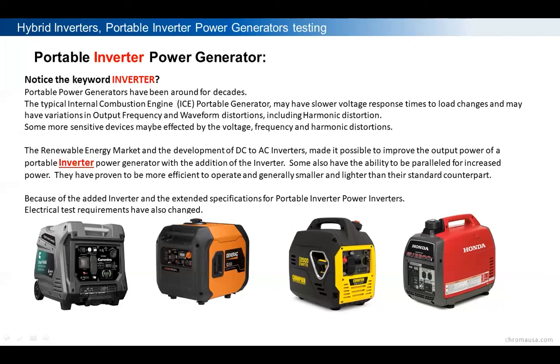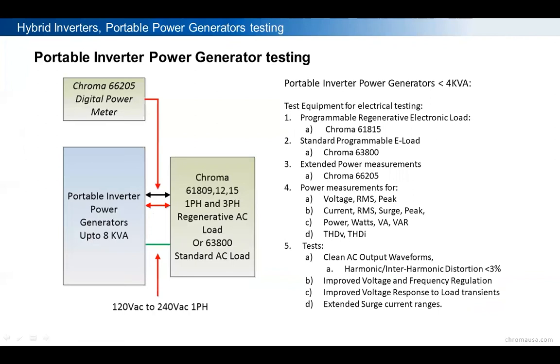Whereas the inverter version of the power generator includes an inverter that takes the AC from the alternator, converts it to DC, and then generates an AC voltage on the output of the inverter. It regulates the voltage, regulates the frequency, has very low noise output and very low harmonic distortion, perfect for so many applications. So to test that unit, you're going to need two devices.